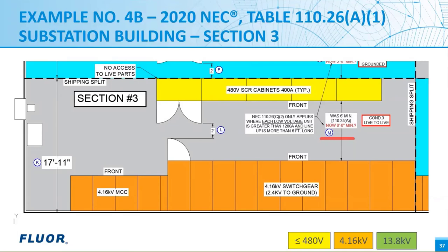For the purposes of our example today, however, we're going to err on the conservative side, and we're going to assume we're only going to need 2 foot minimum clear when the doors of the equipment are open 90 degrees, which separates the SCR cabinets and the medium voltage equipment by 8 feet front to front as seen near bubble L.